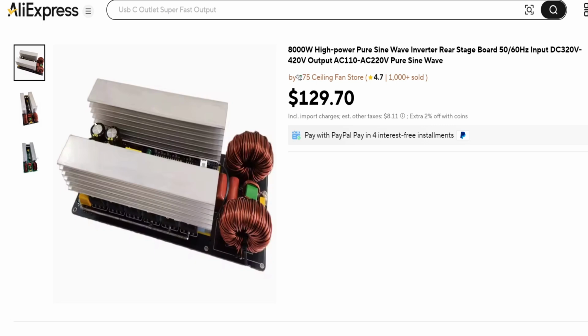There's a massive inrush of current into these capacitors that can be potentially damaging to the capacitors themselves and anything else in the way. So it's necessary, or a good idea, to limit that inrush current so you don't get 1,000 amps when you flip the switch. It can damage your switch, cause pitting, arcing, and all kinds of problems.